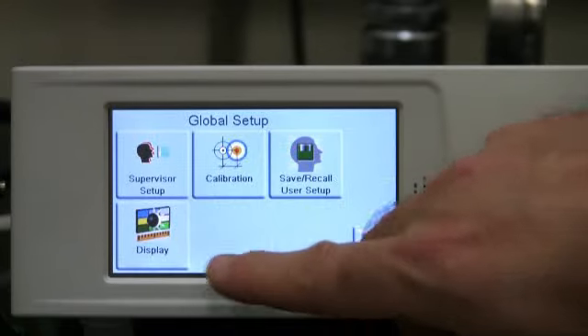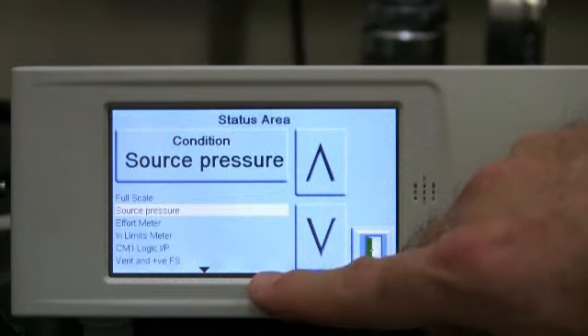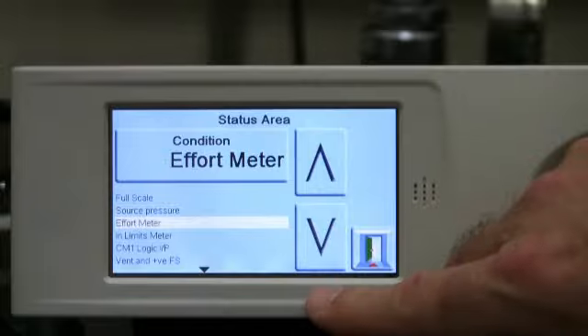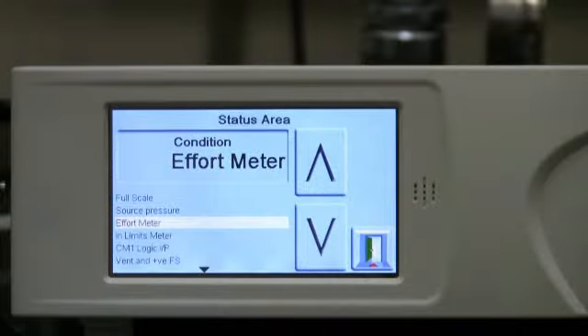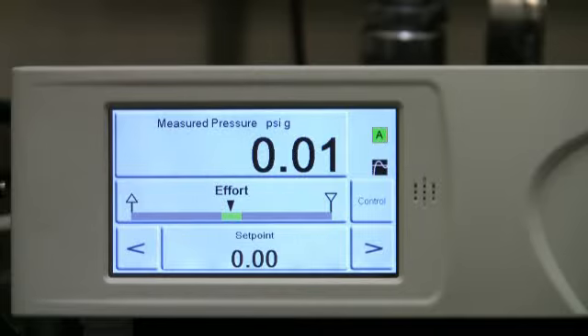Now that the source pressure is set, we will change the center section to display the effort meter, which continuously monitors the activity of the patented pulse width modulated control valves. This will allow us to quickly and easily determine if there is a large leak in our device under test connections. If the effort meter is in the center green section when the set point is reached, all is well. If the effort meter is outside the green area, this is an indication there may be a large leak which would need to be addressed before proceeding with the calibration.